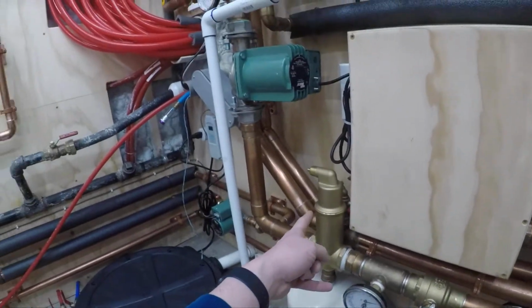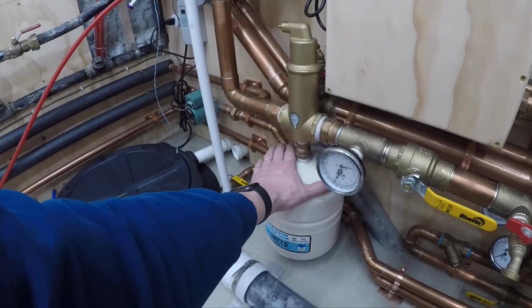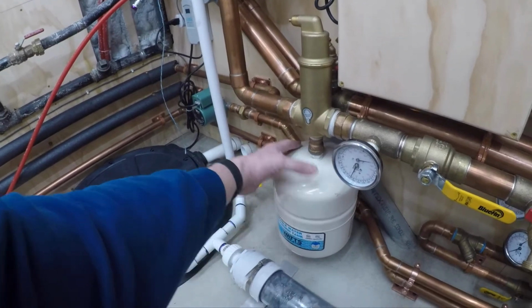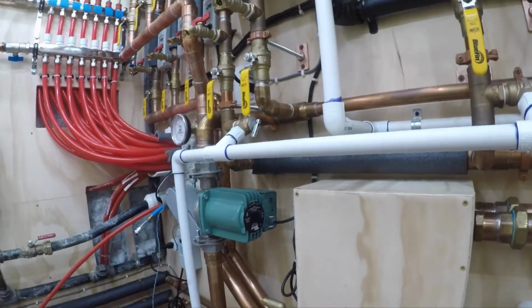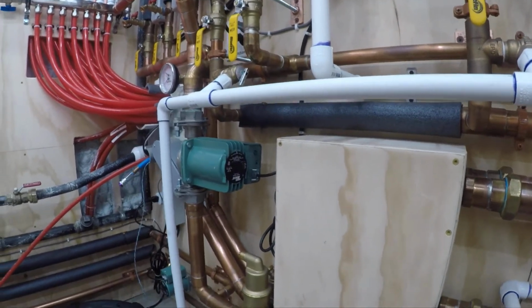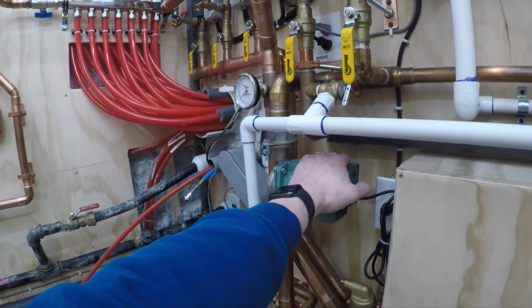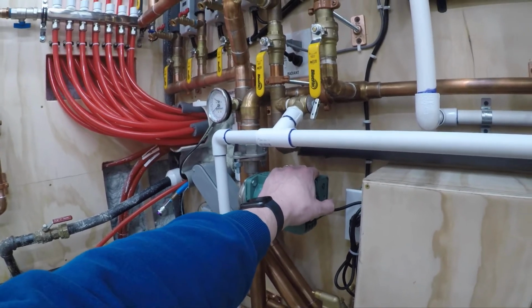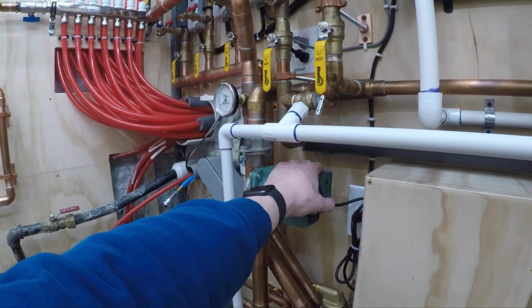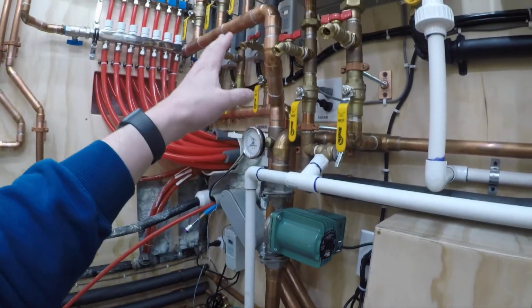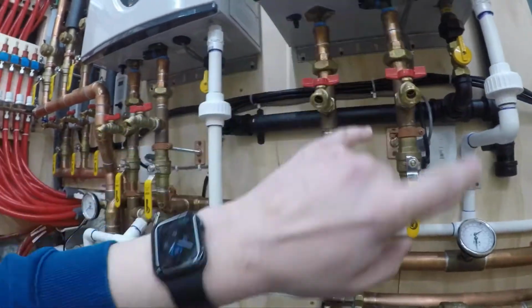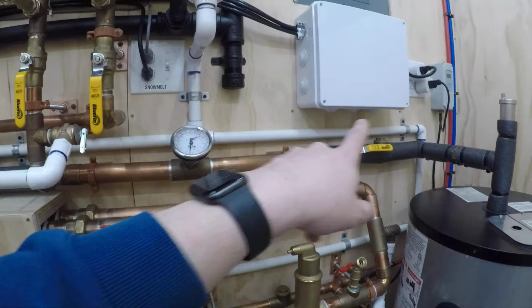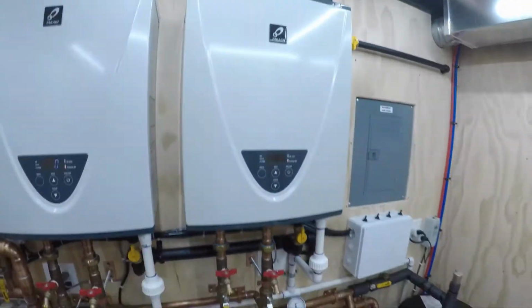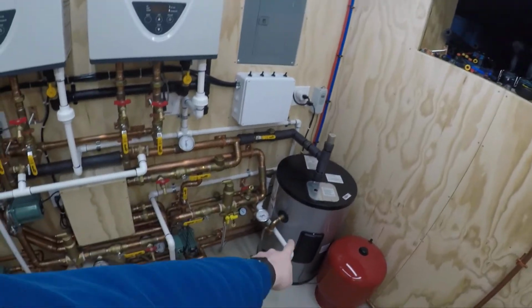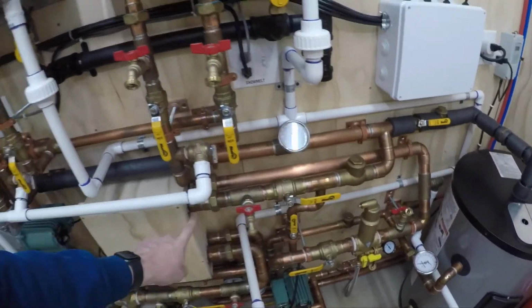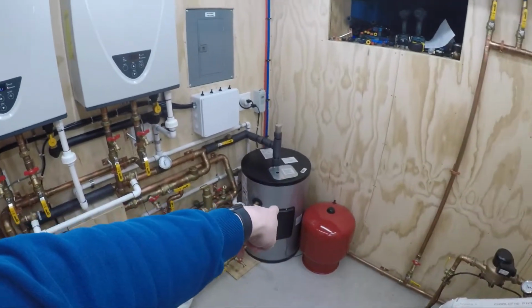Come over here, I have my domestic expansion tank. This is an expansion tank on the domestic side. It's meant for domestic. Handles the pressure increase of the system when this water's heated up. My primary loop pump, which stays off when there's no call for snow melt or radiant heat. This is off. Okay, the water just flows right through it. The water goes into the heaters through the cold, comes out through the hot, and we go back through whatever we're doing. Okay, so if we're heating hot water, it goes right into the tank, comes out of the tank, goes through this pump, up, back in, round and around it goes until that tank is satisfied.